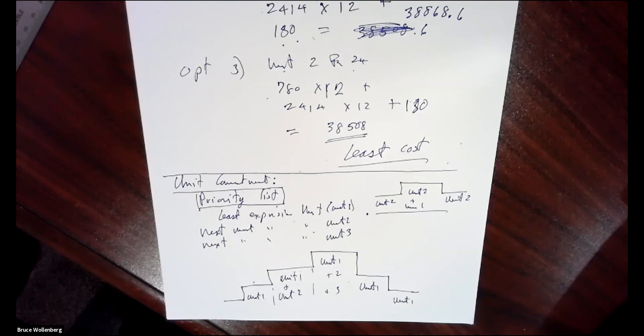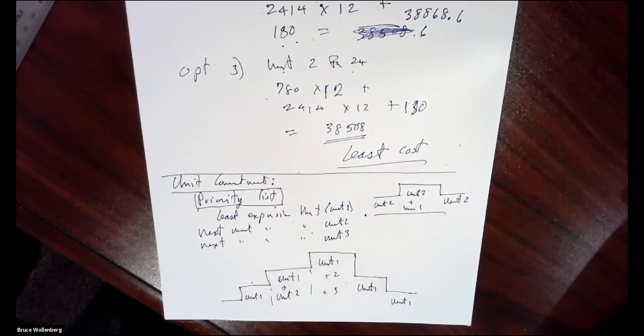It gives you generation, and so you schedule those generators, and then you build your model for each hour and calculate what the generators are going to put out by economic dispatch, and then run the power flow to determine what the transmission loadings are like. But you use something really crude for the unit commitment. It doesn't have to be that accurate. It doesn't have to be the ultimate minimum. So there are good techniques that are fast and reasonably accurate that you use all the time for studies.